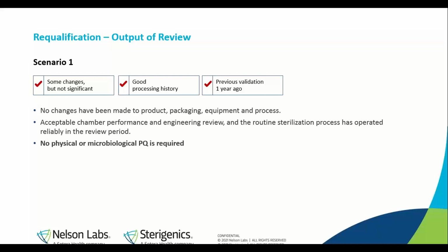After the review, maybe you've identified that there are some changes to the product or process, but they're not significant. You have a good processing history since the last requalification, and the previous qualification was performed 1 year ago. Once again, this would be no changes to the product, packaging, equipment, or process, and there's an acceptable chamber performance and engineering review. The sterilization process is operated reliably within the review period. Well, then no physical or microbiological PQ would be required.